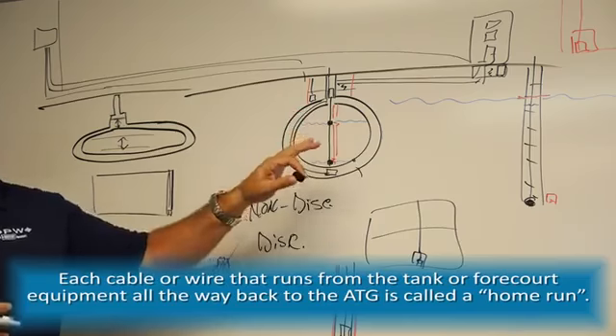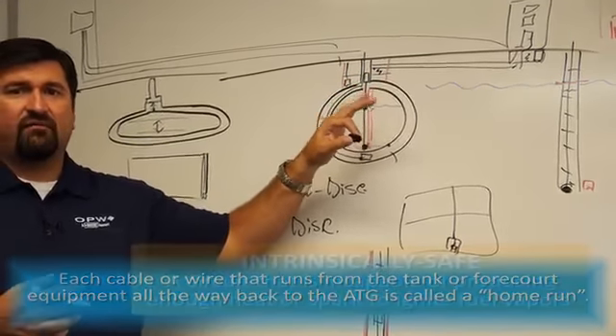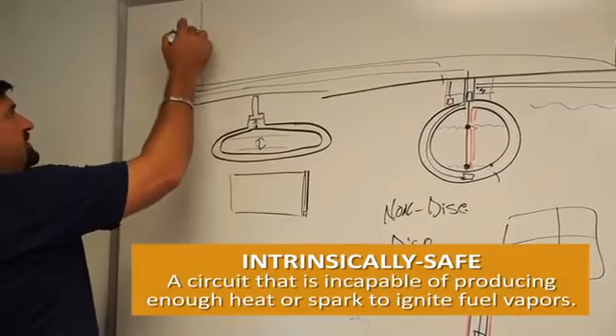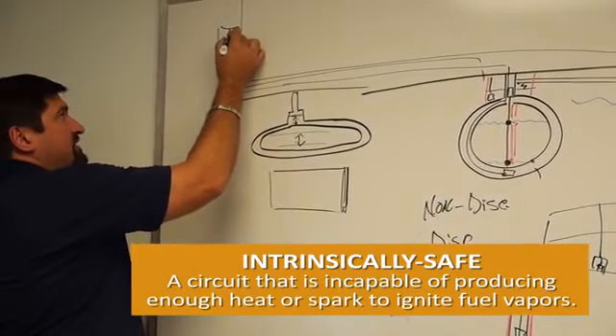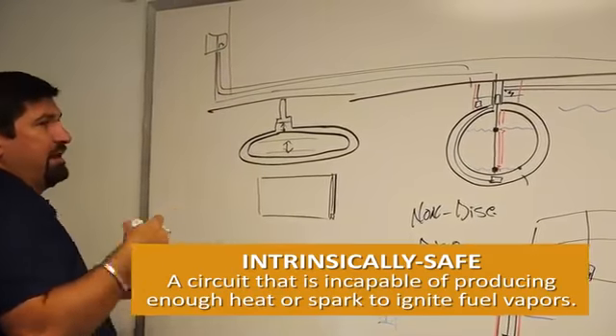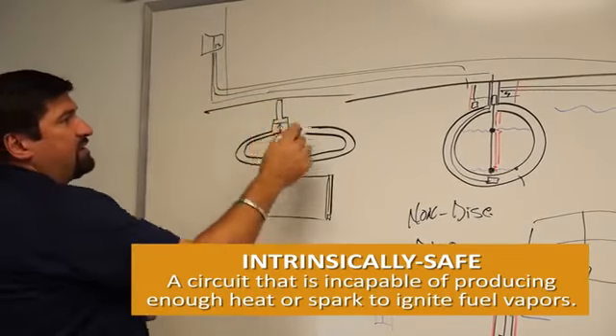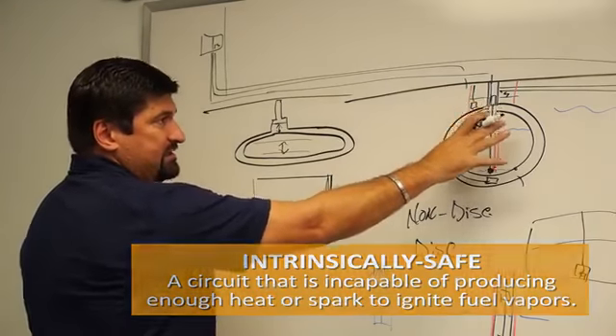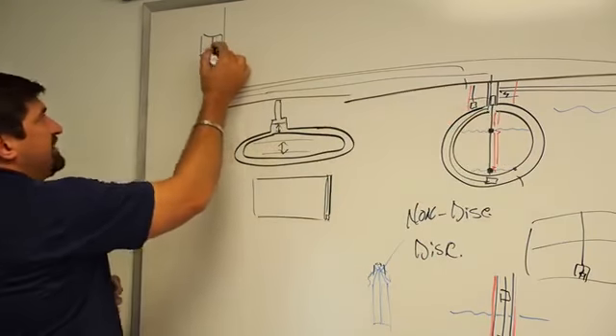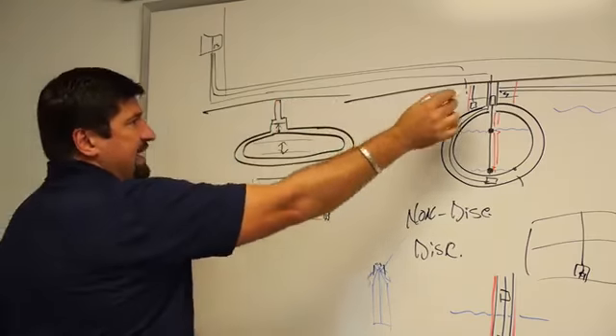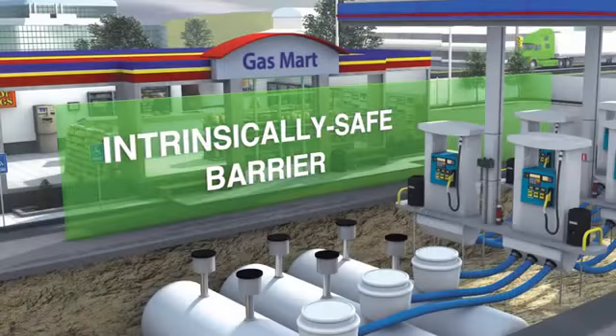But what you have to keep in mind is that we're monitoring fuel. So everything out in the field has to be maintained in an intrinsically safe environment. So inside this console, what you're looking for is some type of IS barrier, an intrinsic safe barrier, that can monitor this and provide power to this out in the field, but still have the ability that if I short this cable out and I just completely cut across it, there is an inability to either create heat or spark out in the field. That's what IS means.